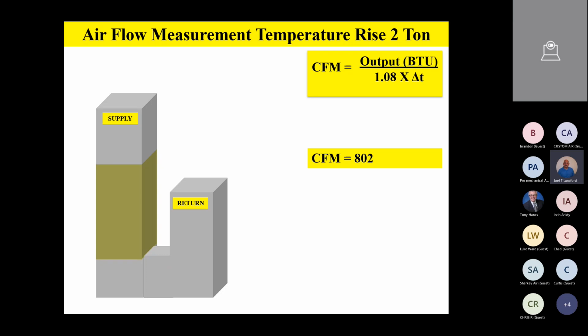I sent along with our printed information a few weeks back when I sent that information out. You should have a quick formula guide that's on there to remind you. But this method of airflow measurement is, like I said, kind of an old-timey method. But it says that if you know the output of the device in BTUs and divide it by 1.08 times the temperature difference of supply and return, that equals your CFM. And by the way, this is going to get you very, very close. If you don't have any other tools on your truck except a temperature probe, a voltmeter, and an amp probe, you can still measure airflow on a unit.